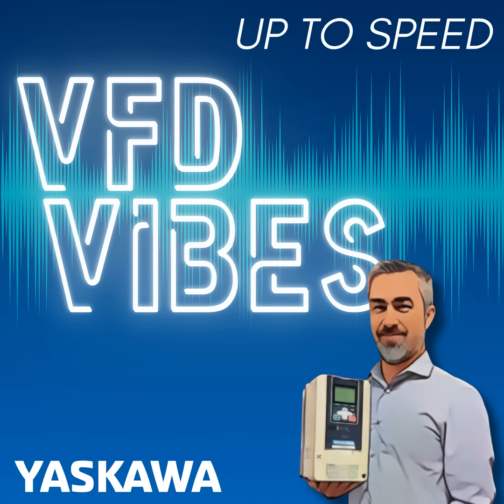Yeah, I would say the biggest things, Greg, would be for customers to understand or try to understand, calculate, determine what their available fault current is, where they want to connect a load, and then make sure that you choose equipment with an SCCR or a withstand rating that's equal to or better than the available fault current. That's a key thing to remember.